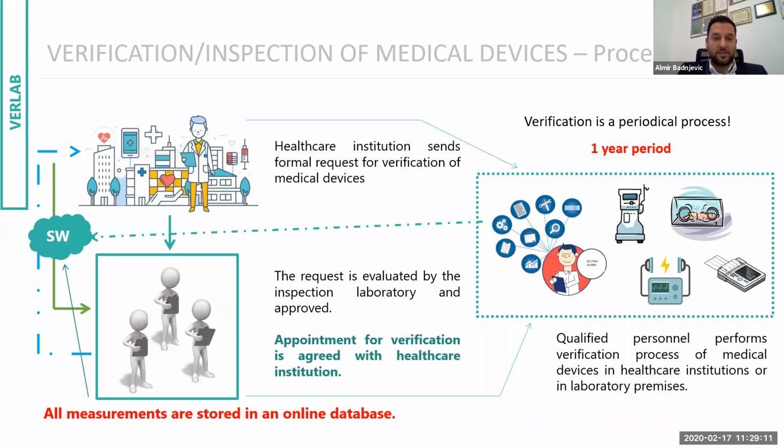What are the process steps? For example, when some healthcare institution wants to do verification or inspection of medical devices, first of all, the healthcare institution sends a formal request for verification of medical devices. Then the request is evaluated by our inspection laboratories, and if it is approved, they appoint the people who will go and measure those devices.